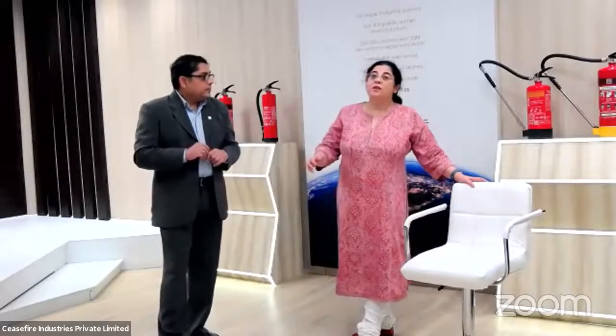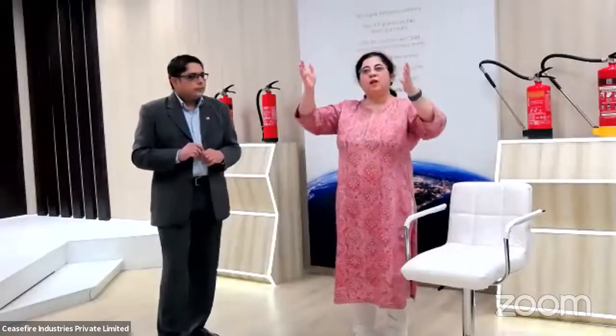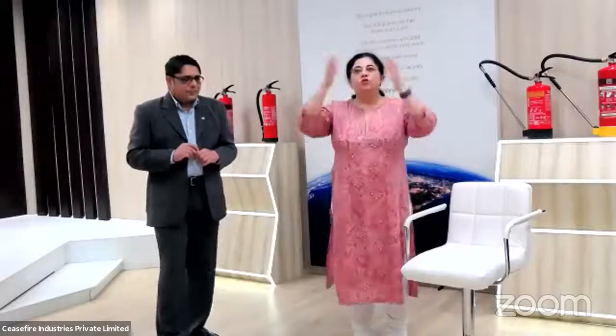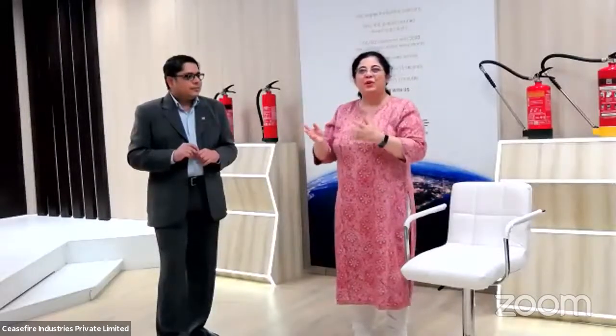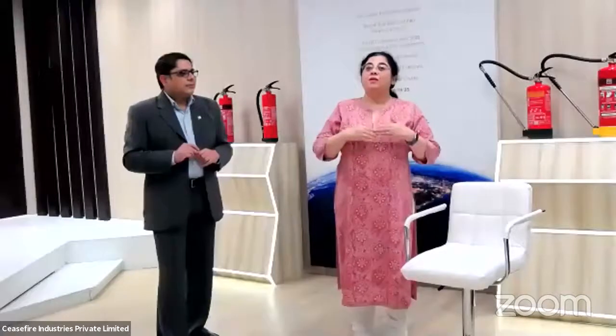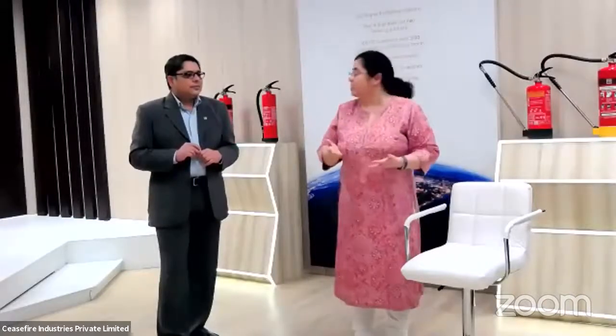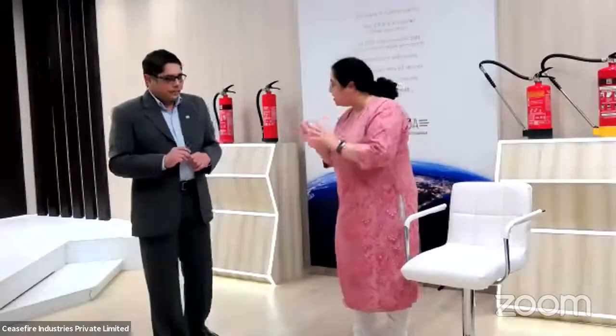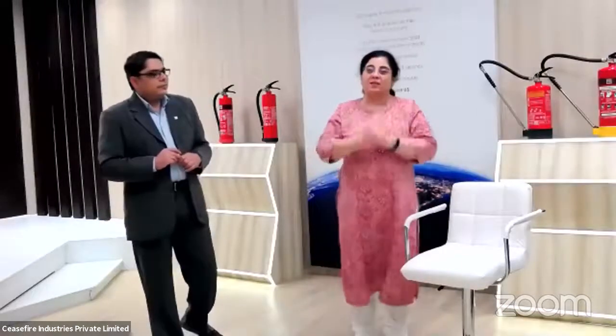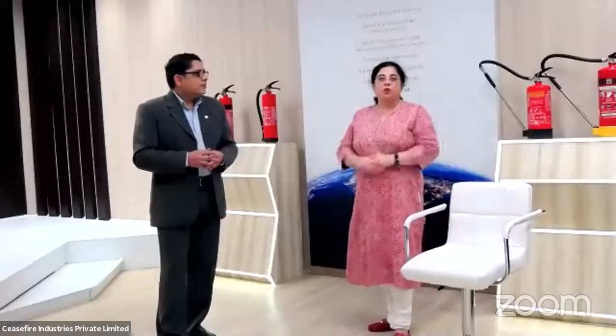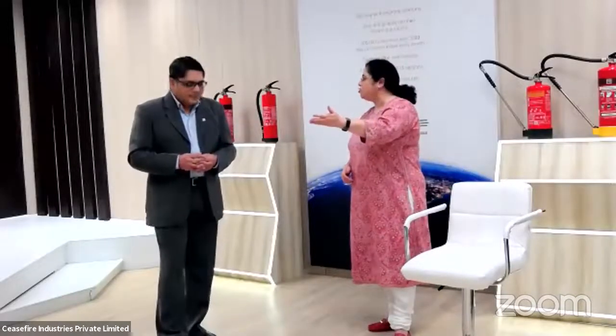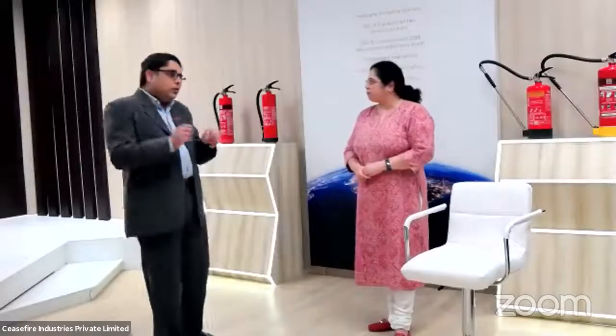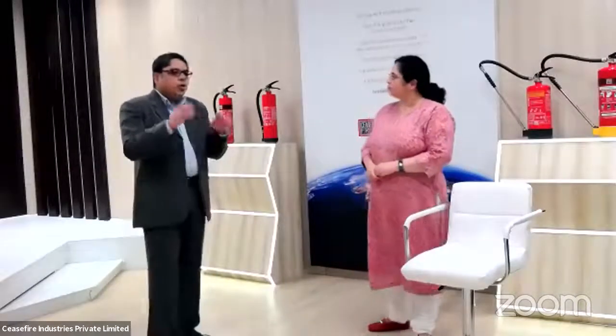So the way I understand it is that wherever the fire happens, there's a puncture in the tube running above that area. The pressurized gas inside the tube is released, activating the suppression system in a way. So this tube is working in two ways. Not only is it acting as a detecting system, it is also activating the system. And the fire gets put out because the agent now flows out of this tube to put out the fire. And this tube is the heart of the whole system, because it is not an ordinary tube.